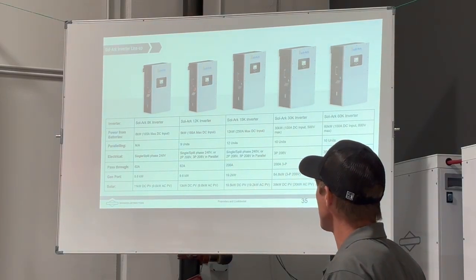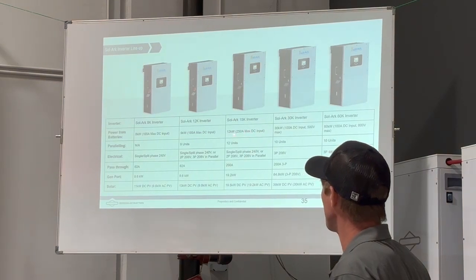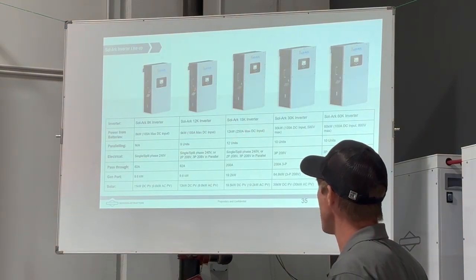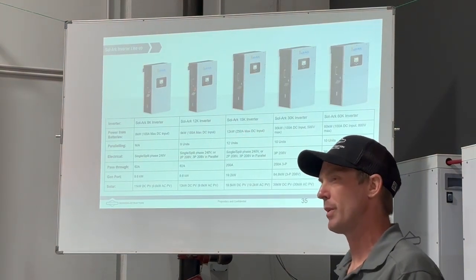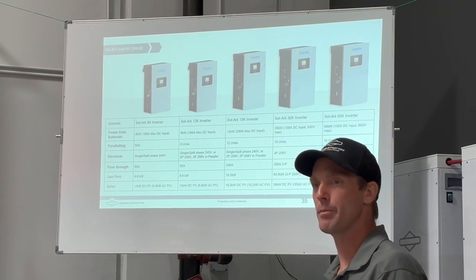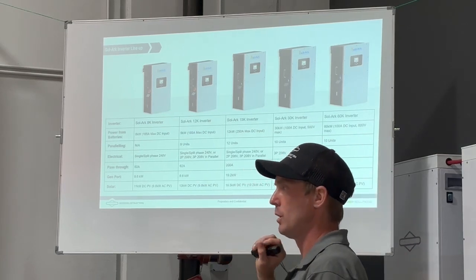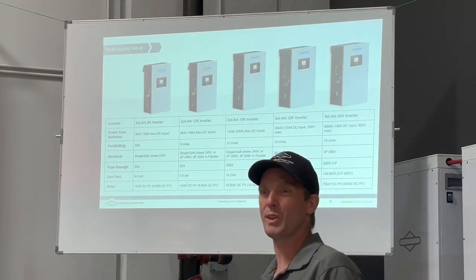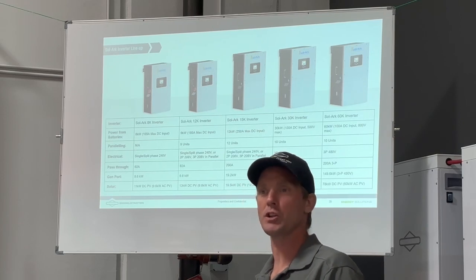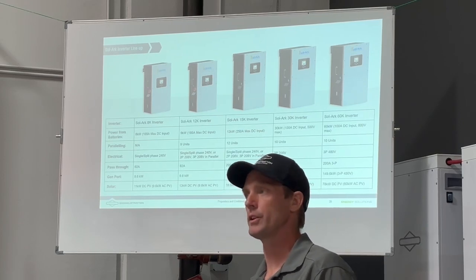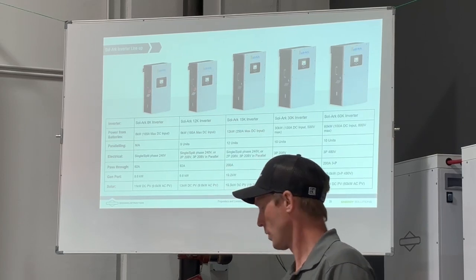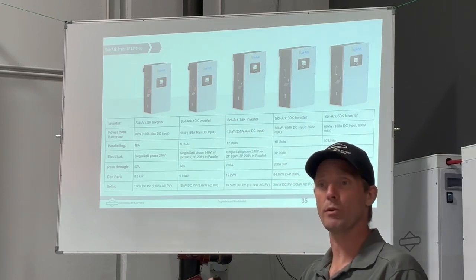So it's capable of inverting 15 kilowatts of power. It will bring in, now we said 250 max DC input. I believe it's 275, but that might be on 275 amps would be with a lead acid battery bank. The limitation is the power, not necessarily the current. So if you had a lower voltage battery, you can bring in more power.